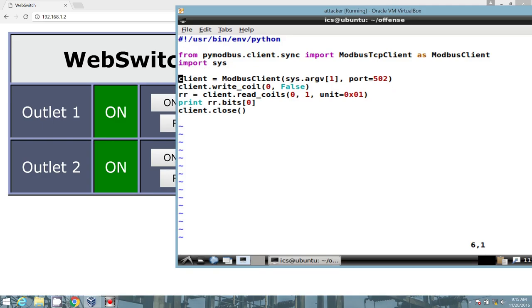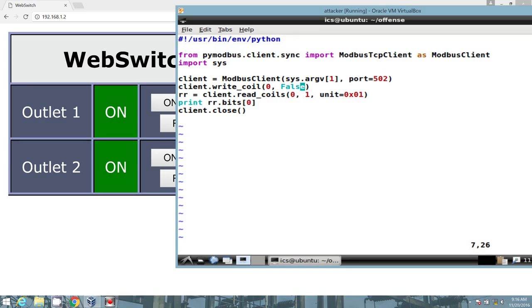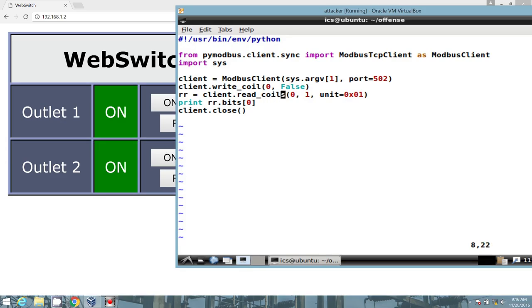And then we establish the connection with the client. We accept a system argument in the command line, which will be the target IP address. And we've hard-coded Modbus port 502. Once the connection is set up, we then write coil to the first address and we pass it the value of zero, Boolean for false. Once we wrote the data into the coils, we then want to read that value and we go ahead and grab the first address, the first bit. And then we go ahead and print that out and close the connection.